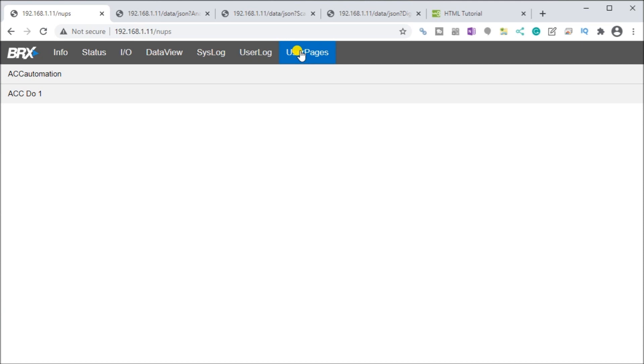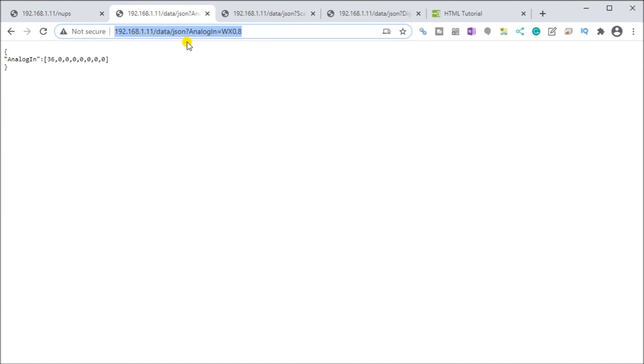The first thing we'll do is take a look at what we call the REST or Do More REST API — REST meaning RESTful API or Representational State Transfer, and API standing for Application Programming Interface. What it is basically is a URL that we can ask for information out of the BRX Do-more PLC. Here we specify our IP address 192.168.1.11, ask for data in JSON format, and give it a variable name — in this case analog in, starting at WX0, asking for eight values, which comes back as a JSON array.